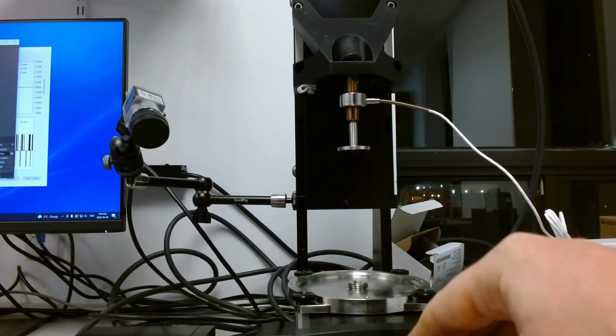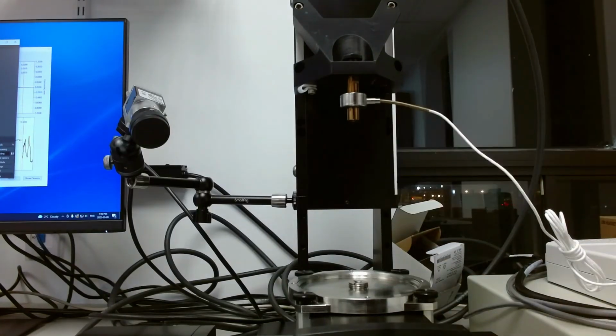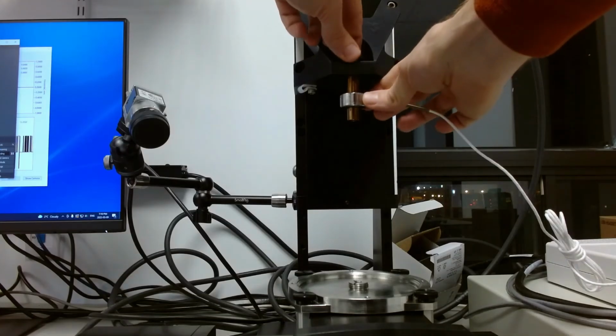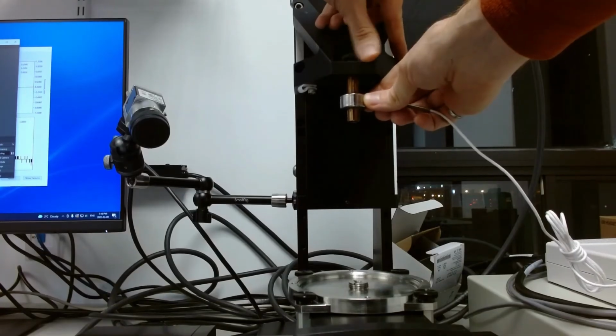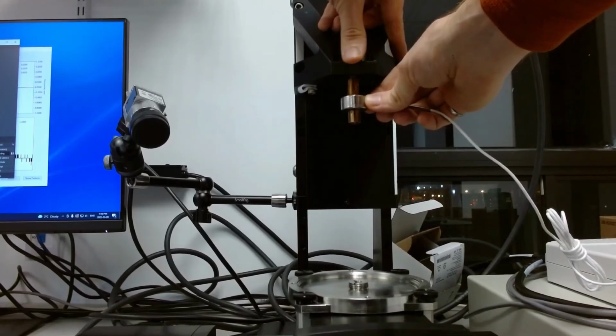If there are multiple people in your lab or facility that are using this machinery, I would recommend uninstalling the load cell at the end of the day and keeping a log of who uses it and what calibration factor is measured that day.